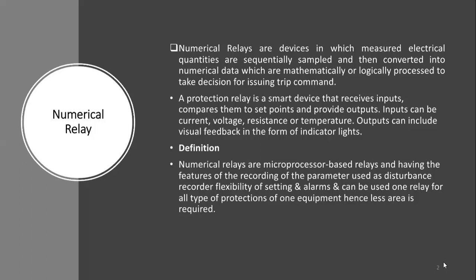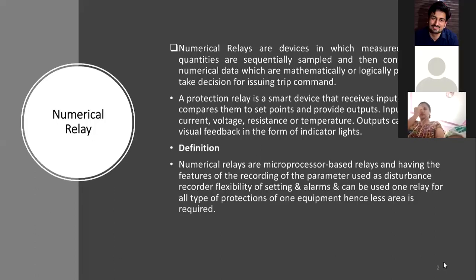We can define numerical relays as microprocessor-based relays having features of recording parameters, used as a disturbance recorder, flexibility of settings and alarms, and the ability to use one relay for all types of protection of one equipment — hence less area is required. In a numerical relay, there is a microprocessor and memory included, so we can save data, programs, and preset values. The relay compares measured values against preset values to decide: if the current exceeds the set value, it will be an over-current fault; if it decreases below a set value, it will be an under-voltage fault.